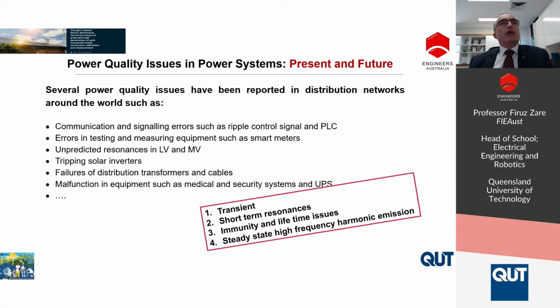So when we are talking about high frequency harmonic issues, in fact, we are talking about short-term resonances or transients. We are talking about immunity or lifetime issues, where two devices can interact together. And the other one is the steady state high frequency harmonics. It can be for hours or it can be for minutes.